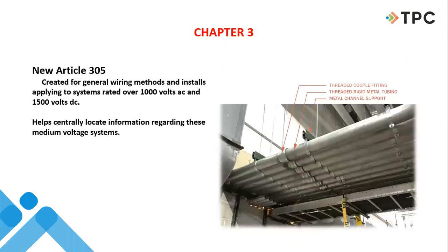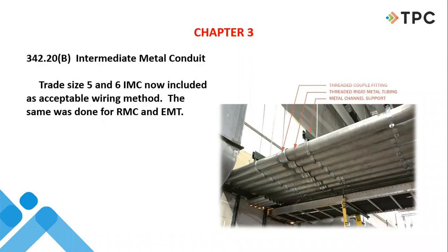There's a new Article 305 out there that was created for general wiring methods and installs applying to systems over 1,000 volts AC and 1,500 volts DC. The goal is to centrally locate information for what we're going to call medium voltage systems. The code has begun to expand a little bit in these little niches. IMC, trade size 5 and 6 IMC is now included as an acceptable wiring method. Same was done for RMC and EMT.